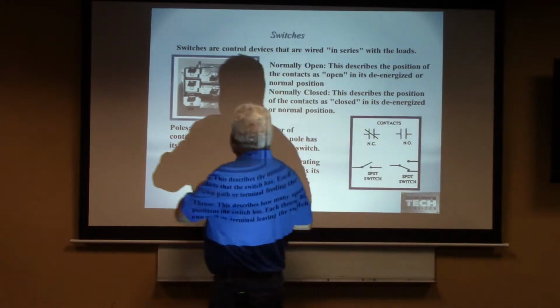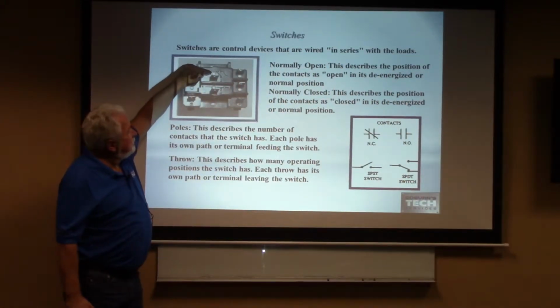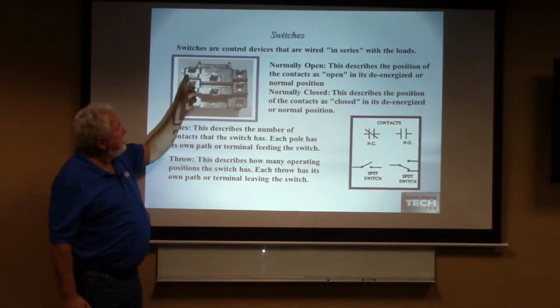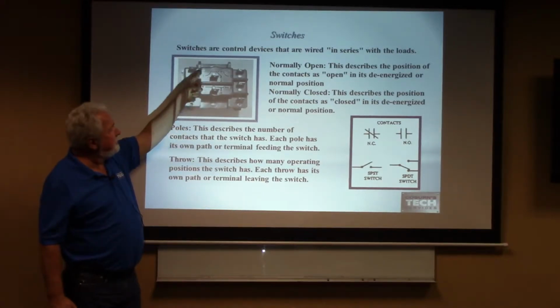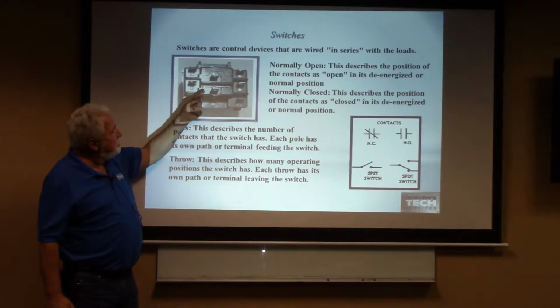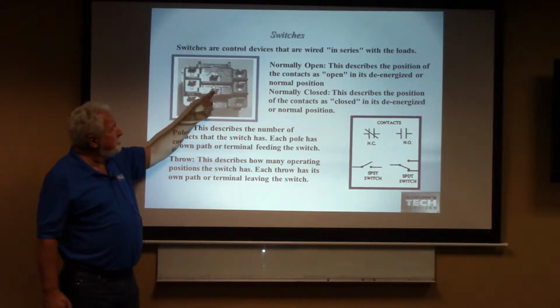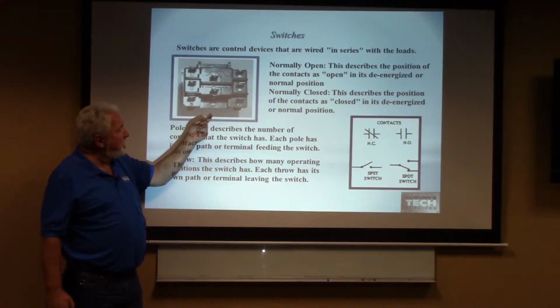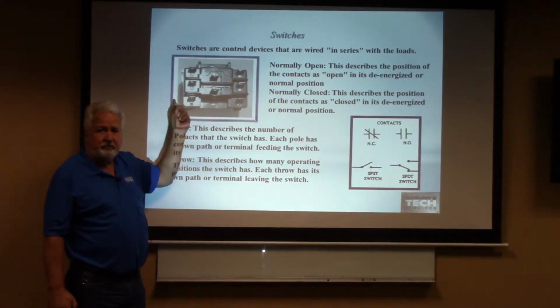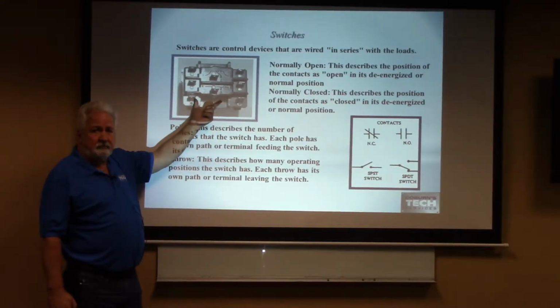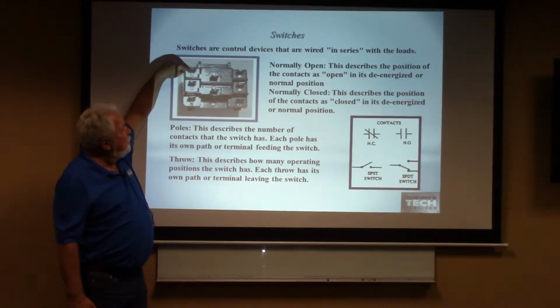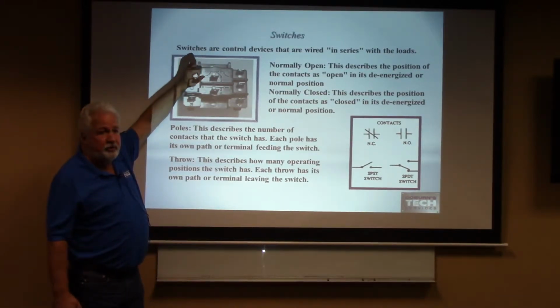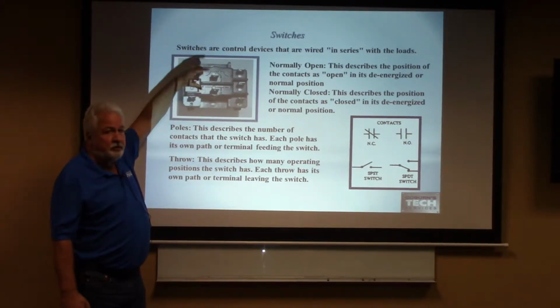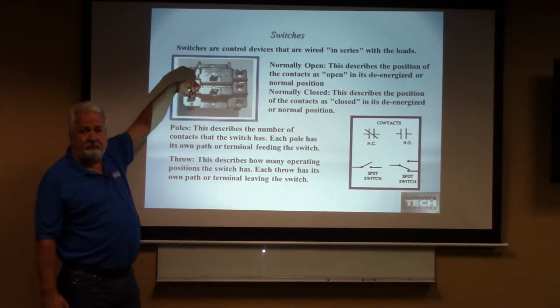So inside this type of switch, look at this up here. We've got a common going to a normally open switch, and we've got a common going to a normally closed switch. You see that? Then this one is a common going to a normally open switch, and this is a common going to a normally closed switch. And this is that coil of wire that runs down at the bottom. That's the magnet part of that switch. In this case, the 24 volts would be applied here. The switch would close, and 1 and 3 would now make, and 1 and 2 would open. 4 and 6 would make, and 4 and 5 would open.